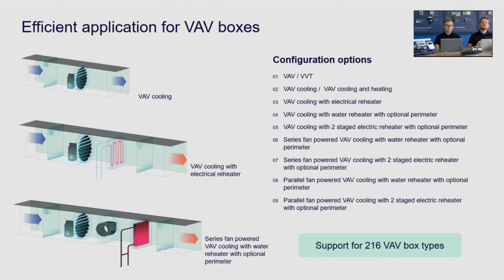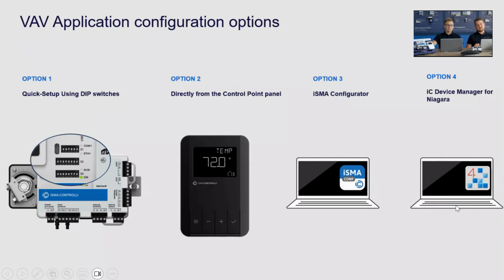So how would you configure the VAV controller itself? Well, we have 4 configuration types for our VAV controller. The easiest one doesn't require any software at all. You can use the built-in DIP switches for the quick setup and initial configuration of the VAV controller. So just setting up one of those 3 DIP switches, you have the access to configure the application.